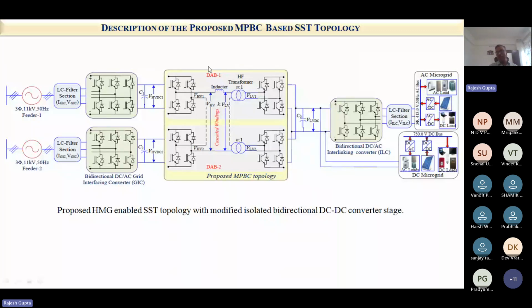Let's say you have 300 volts on this side, 400 volts on this side, and 48 volts on this side to charge a battery. Now if you don't use a transformer, you're right, I can use AC to DC conversion, then DC to AC, and then DC to DC conversion. But then the DC to DC converter has to handle 400 volt to 48 volt, a 10 times reduction in voltage, and if you use this type of converter, the efficiency will fall down drastically. This is where a transformer plays a very vital role: it steps down the voltage with very good efficiency, 95%, using a high frequency transformer. So that's the detailed answer to your query.